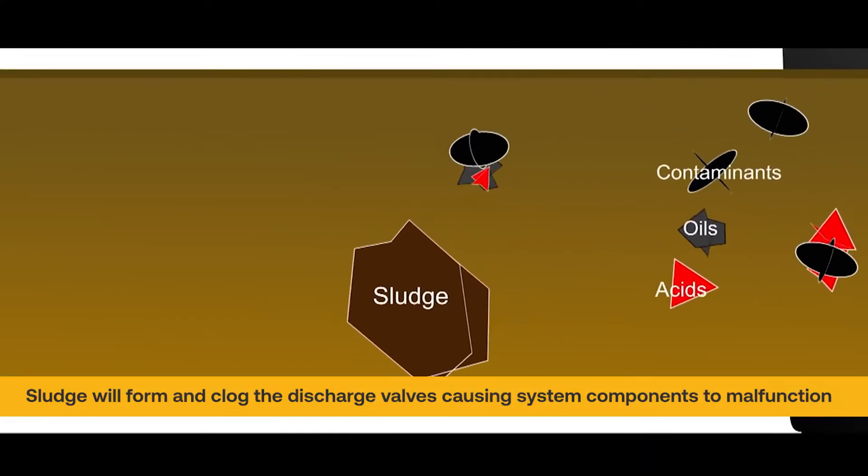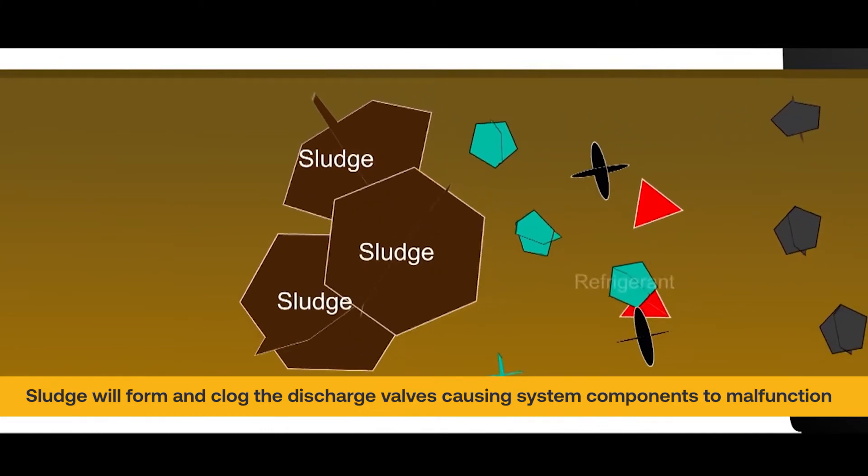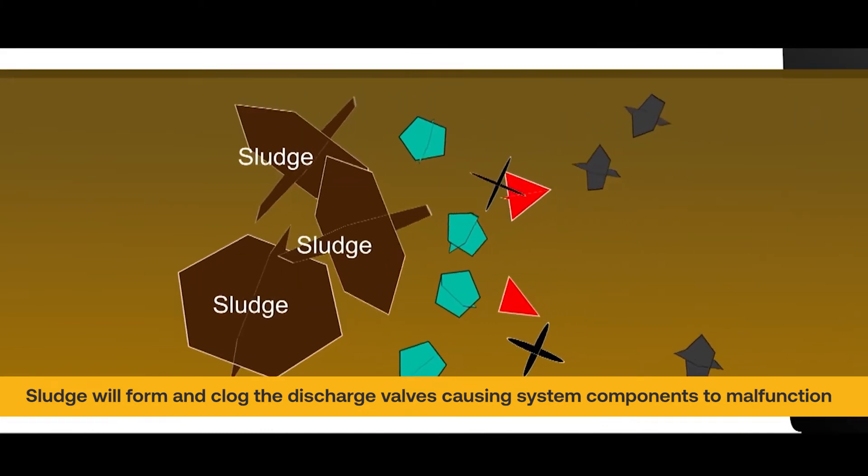Sludge will form and clog the discharge valves, causing expansion devices, filter dryers, and strainers to plug and malfunction.